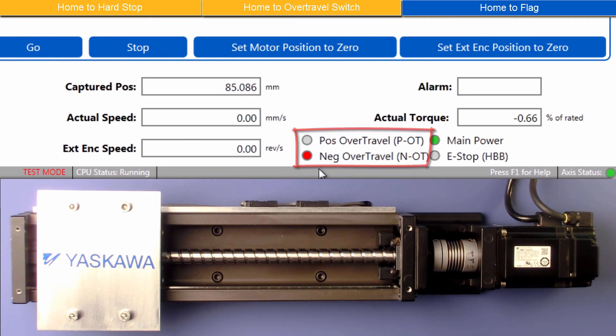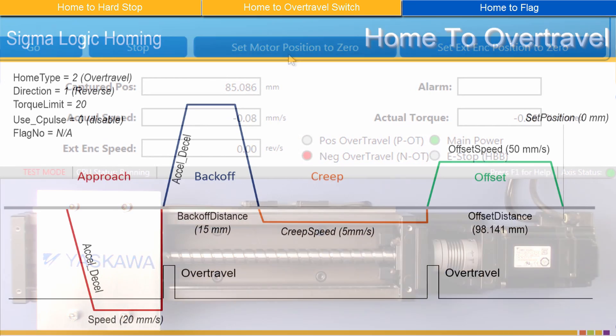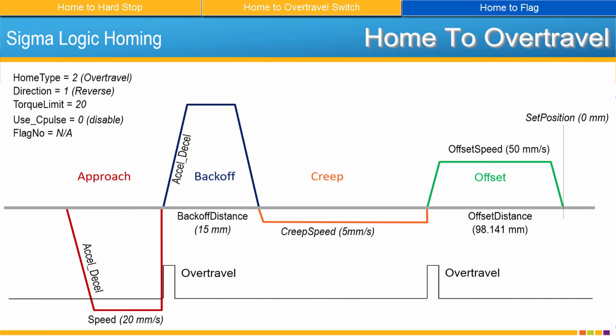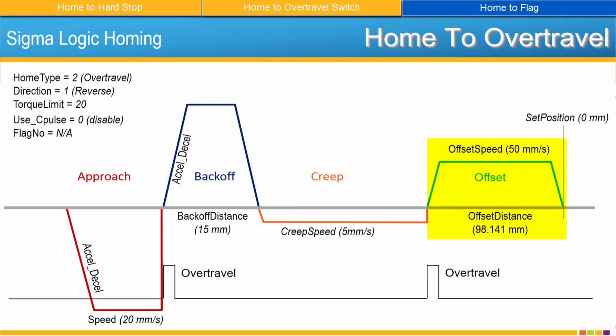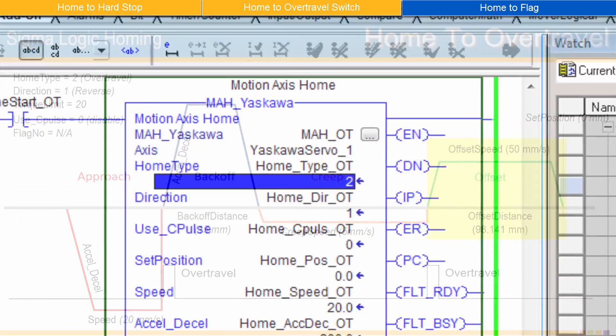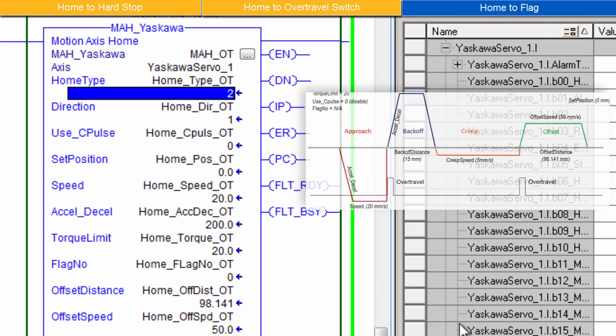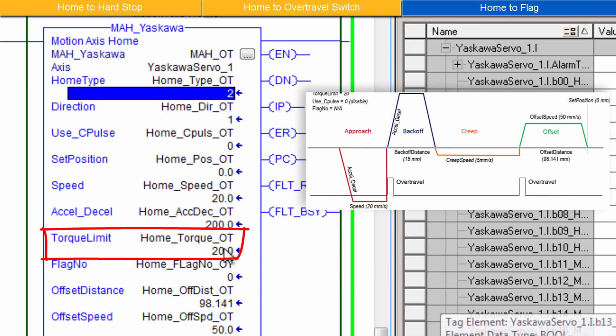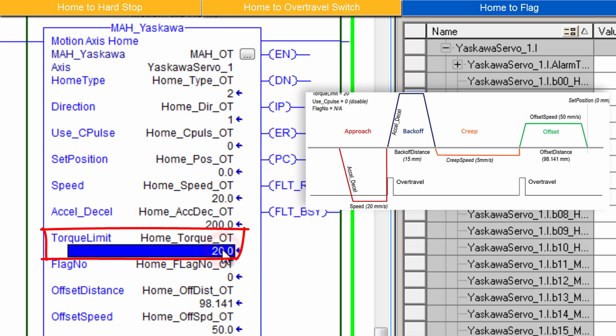Home to Over Travel consists of a sequence of 4 moves. Approach, Back Off, Creep and Offset. I'll set the AOI parameters in the order of this move sequence. Torque Limit applies to the entire homing sequence and must be set to 5% or higher. I'll use 20%.